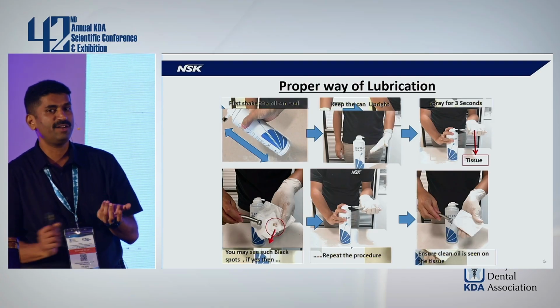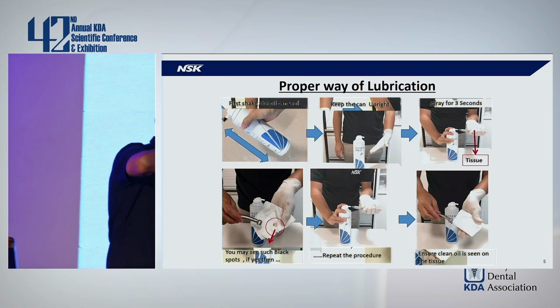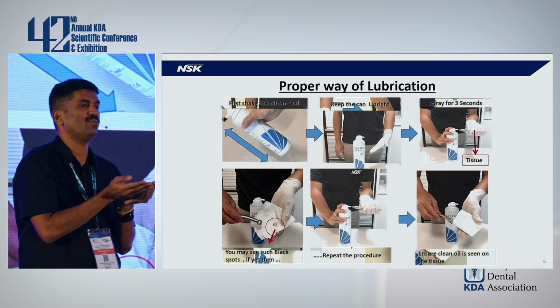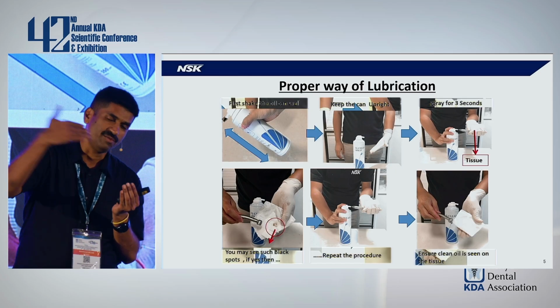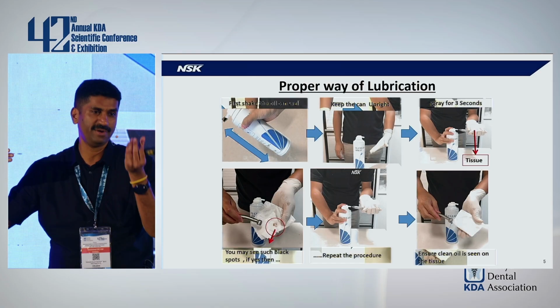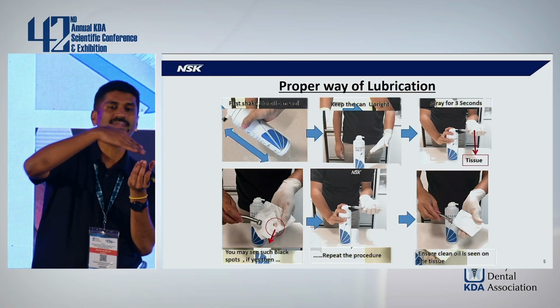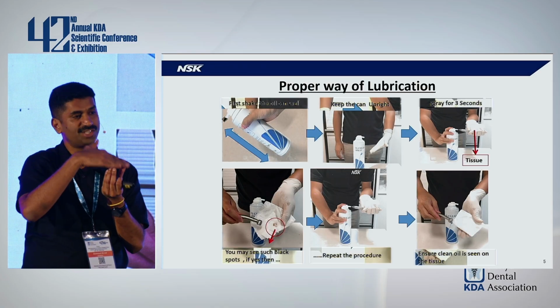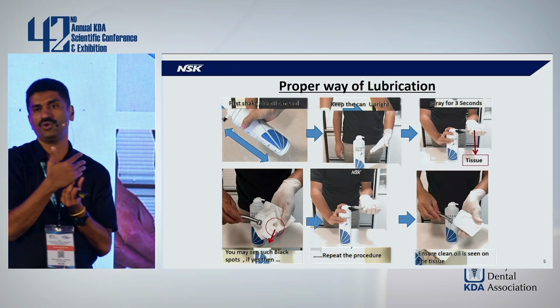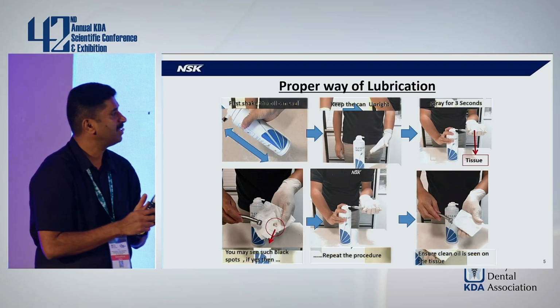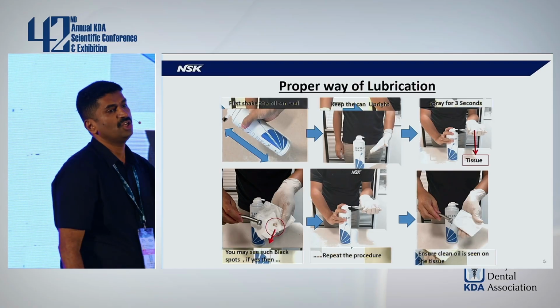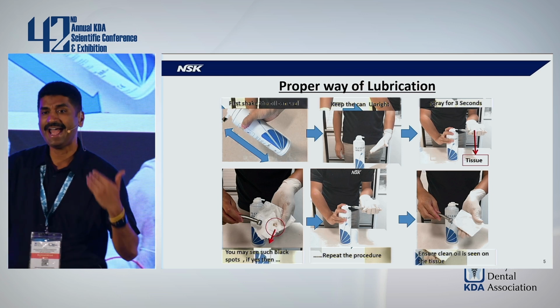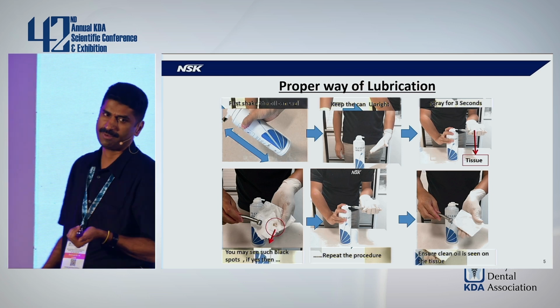Whereas on the other hand, when you do the lubrication, there will be a layer of oil covering this ball bearing, thus protecting this particular retainer, that is the plastic, from getting affected by the steam which is generated during the sterilization procedure. So that is the reason we recommend you lubricate two times a day and every time before autoclaving.